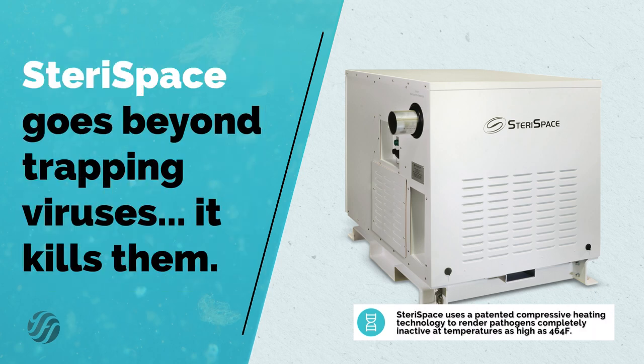SteriSpace doesn't trap the pathogens, but actually kills them by using compressive heating technology. This technology has been tested and validated extensively through funding by the U.S. Department of Defense and has repeatedly demonstrated an effective kill rate of 99.9999%, achieving a sterility assurance level of 6 log reduction.